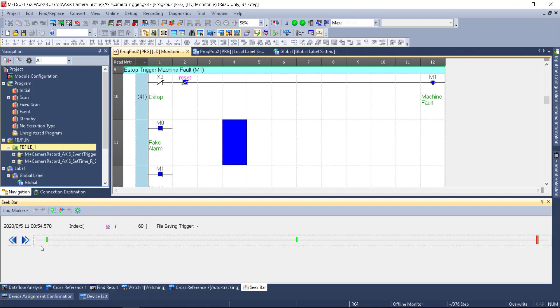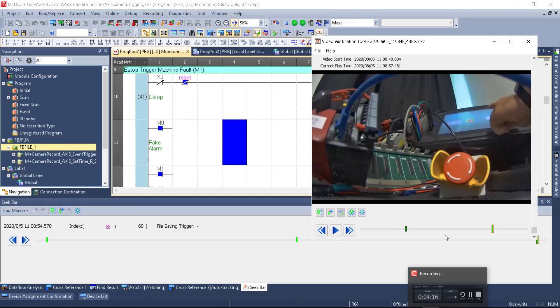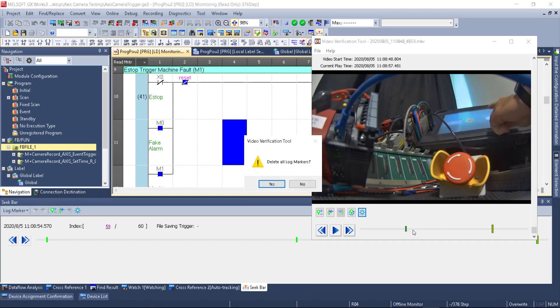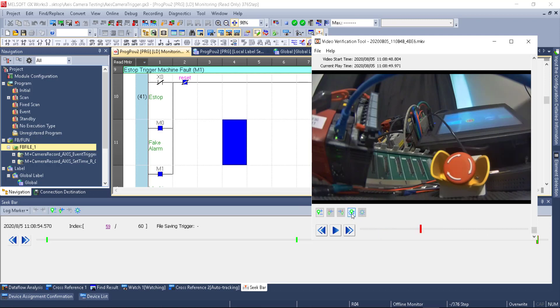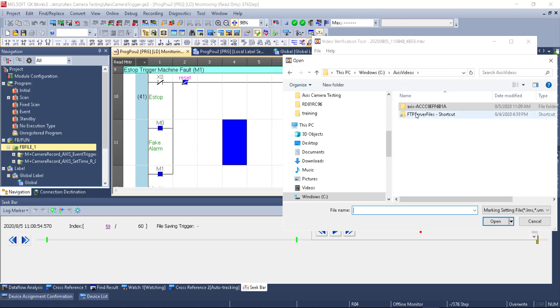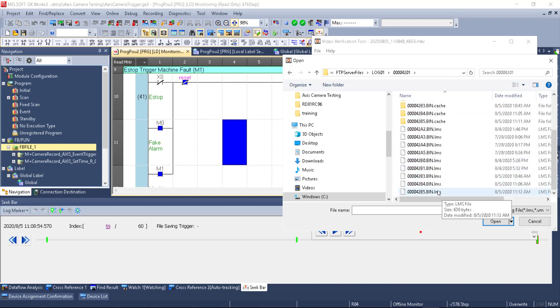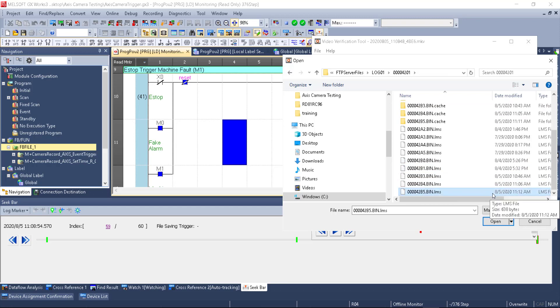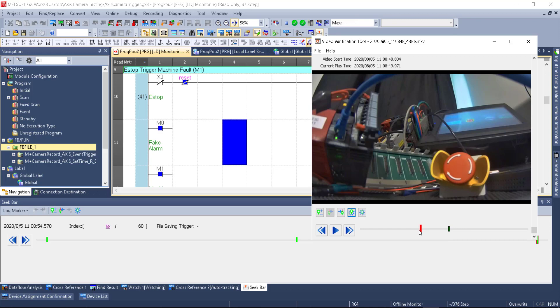I add log markers at the beginning, middle, and end — those are permanent and stay with that file. Going back to the Video Verification Tool, I delete existing markers and then read the GX Works 3 log marker file from the log folder. The LMS log marker files are at the end of the folder. I select the latest one, and now I see all three log markers grouped tightly together — this is why it's critical to have the CPU time-synced with the video file, matching down to the second.